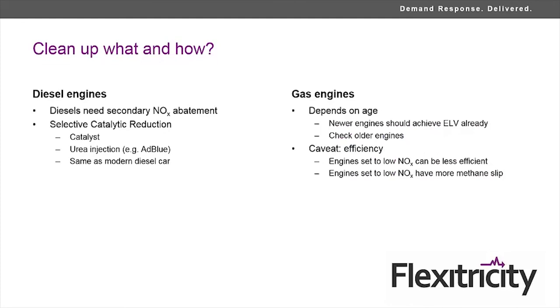There's one other caveat that needs to be put in place here, which is that while it is possible to set a gas engine to achieve these emissions limits, the result of doing so can be to make the engine less efficient, and it can also cause a further increase in methane slip. Methane slip is the phenomenon of incoming fuel which is not fully burnt in the engine, and that has a cost and an environmental implication. So in fact, potentially the best practice for a gas engine is actually to set the engine to high efficiency, which means the completeness of combustion is greater, the efficiency is higher, but the NOx level in the immediate exhaust of the engine is higher - and then fit selective catalytic reduction, so that the NOx is then brought back down.